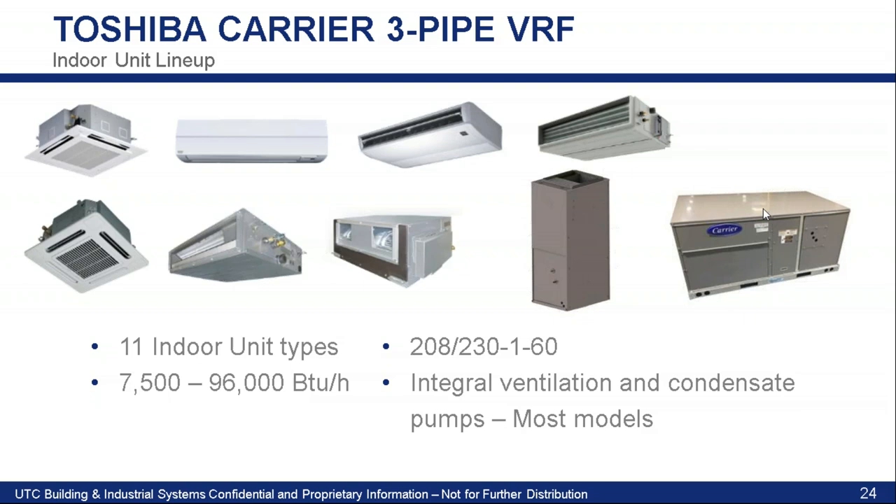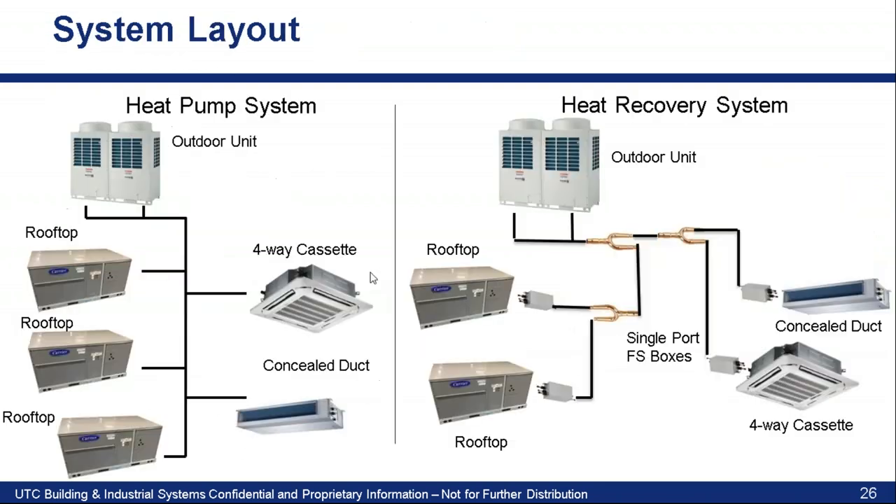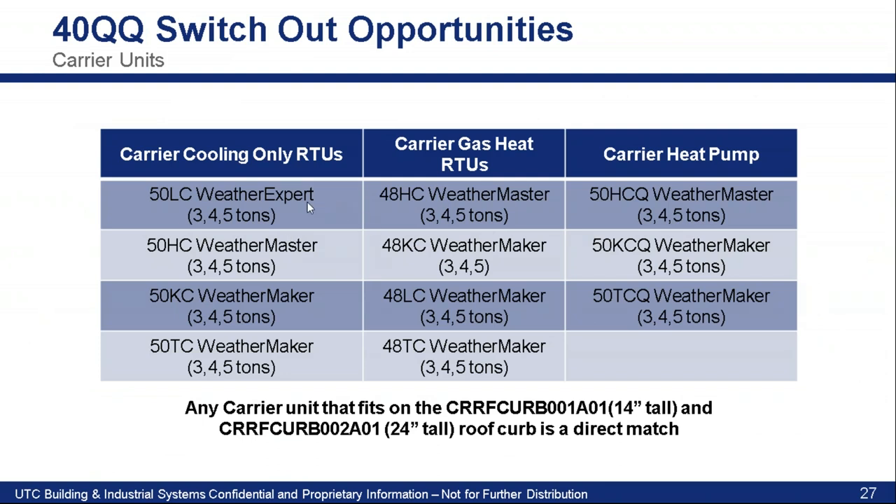Carrier actually has a rooftop unit now that can tie into a VRF outdoor unit. It does not even have a condenser coil at all. There are also manufacturers that have unit vents. Because of the efficiency with the refrigerant, you're going to see more and more indoor units that are compatible. This Carrier rooftop unit is available in three, four, and five tons, no condenser coil, so it's a lot lighter. Available in 208 single phase or 230 single phase, no three phase option. It has an ECM motor with three speeds, good external static, and it will fit on existing Carrier rooftop curbs.